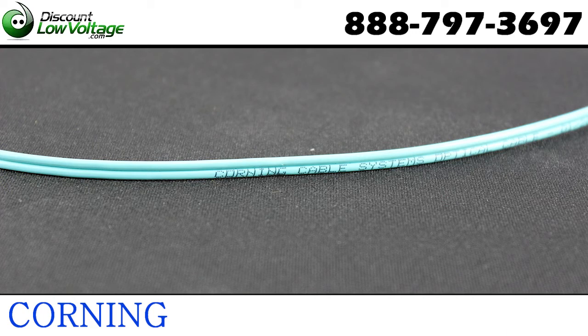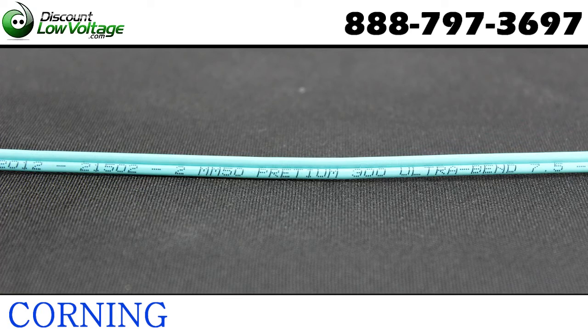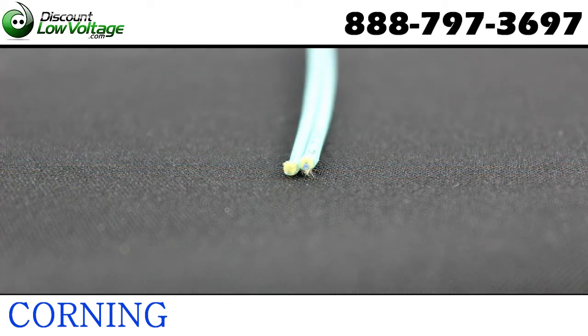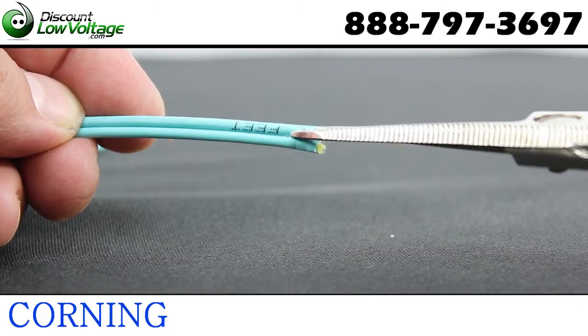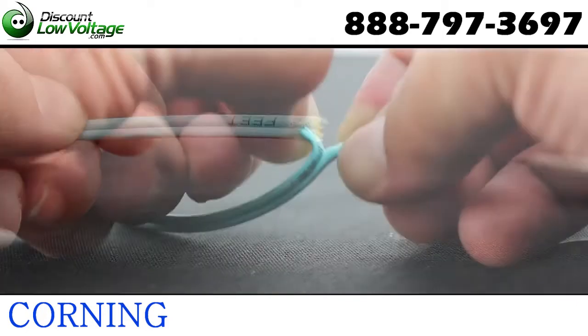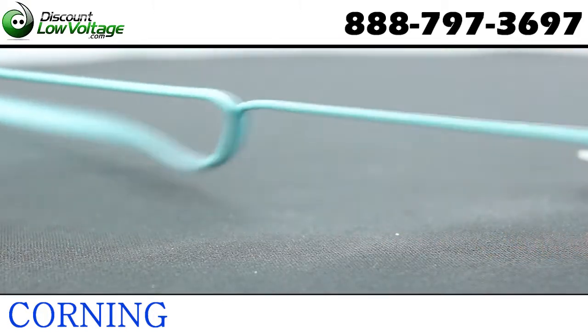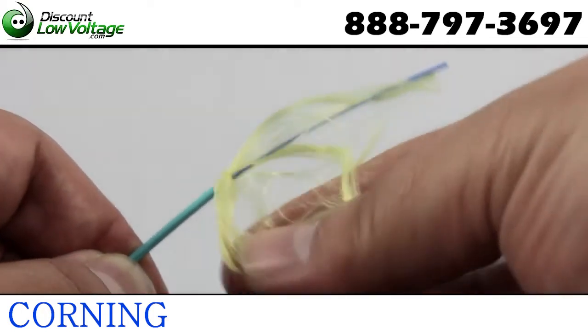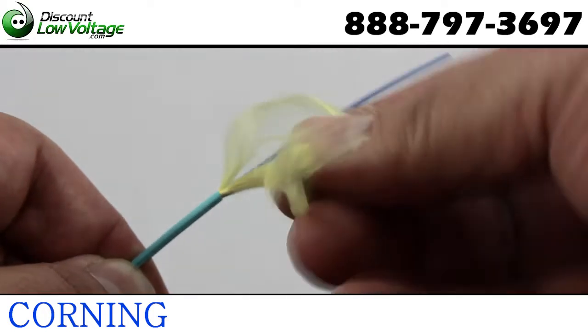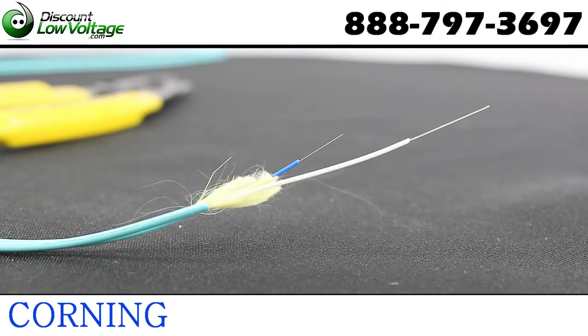This Corning Zip Cord Type Buffered Cable is a two strand with a two millimeter jacket on it. These cables are designed for interconnect applications. Two 900 µm tight buffered fibers are surrounded by aramid yarn strength members and a flame retardant jacket. This cable design offers mechanical durability and flame resistance that meets the requirements of National Electric Code Article 770.